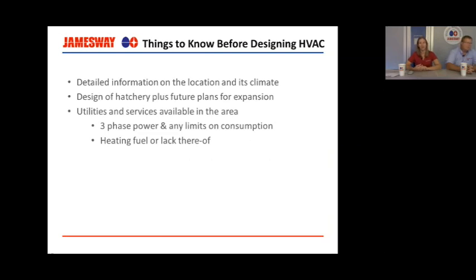So now, switching gears to the customer who is building a new hatchery, you need to design some HVAC. What do we need to know? The first thing you need to know is detailed information on your location and the climate in that location. The other thing that I always like to know is, what are your future plans for expansion? If you're going to put in 6 P60s in a room and in the future expand to 9 P60s in that room, or in the future expand to 12 P60s in that room, I'm going to design the HVAC differently because I always want the rooftop units or the AHUs in the room to be the same size.